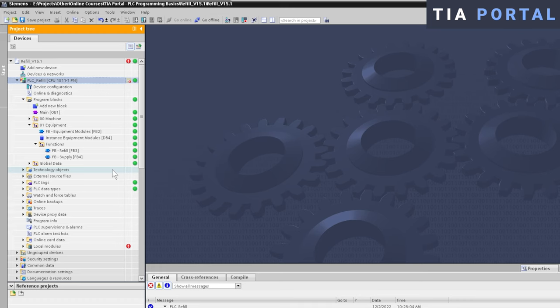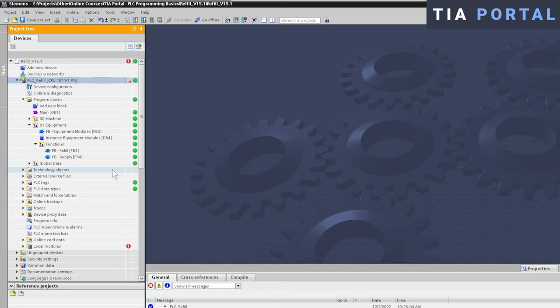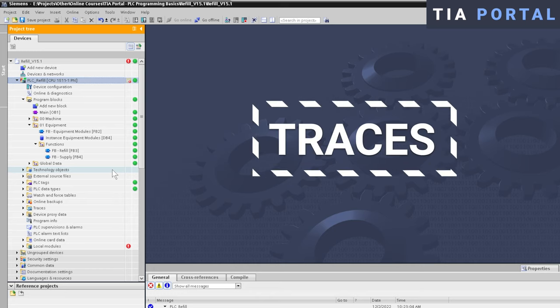Furthermore, tags can be forced in a force table, like for example the forcing of a valve output. So these are two important troubleshooting monitoring tools that are available for both platforms. But there's a third tool, the one tool that TIA Portal has and Simatic Manager does not have. And personally, this is my go-to tool for troubleshooting. I am talking about traces. With traces you can define a set of tags, a set of variables, and then record those over time.